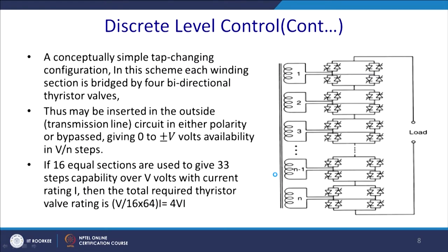So, this is a case of a discrete level voltage regulator. What happens? You can have n number of secondaries and they have been cascaded. So, you have different levels, and you can bypass a particular level, or you can take the level through the magnetics and thus step it up or step it down. And in this case, if one or two or any level is not used, the turns ratio of primary to secondary gets decreased or increased according to the requirement.